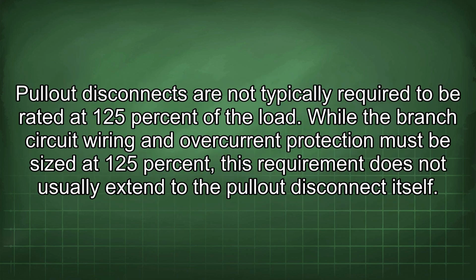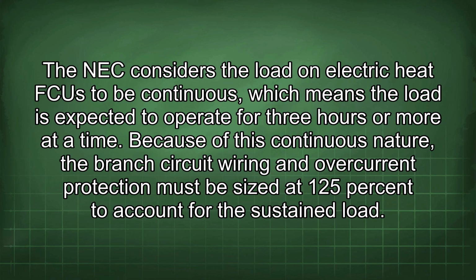Pull-out disconnects are not typically required to be rated at 125% of the load. While the branch circuit wiring and overcurrent protection must be sized at 125%, this requirement does not usually extend to the pull-out disconnect itself. The NEC considers the load on an electric heat FCU to be continuous, which means the load is expected to operate for 3 hours or more at a time.